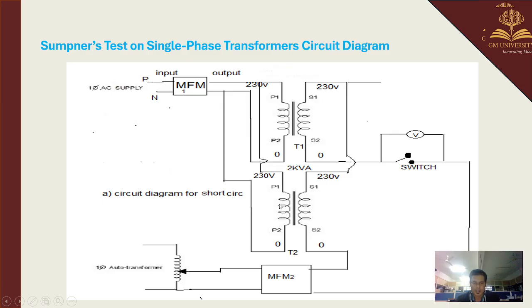On the other side, you can see there is one more single phase auto transformer. The output of this auto transformer should be connected to the input of multifunction meter 2. Then of the output terminals of multifunction meter 2, one terminal should be given to the switch. We have to connect a voltmeter across the switch. The other end of the switch terminal should be connected to S2 of the T1 transformer. S1 of the T1 transformer and S1 of the T2 transformer should be made a common point. Then S2 of the T2 transformer should be connected to the remaining terminal of multifunction meter 2.